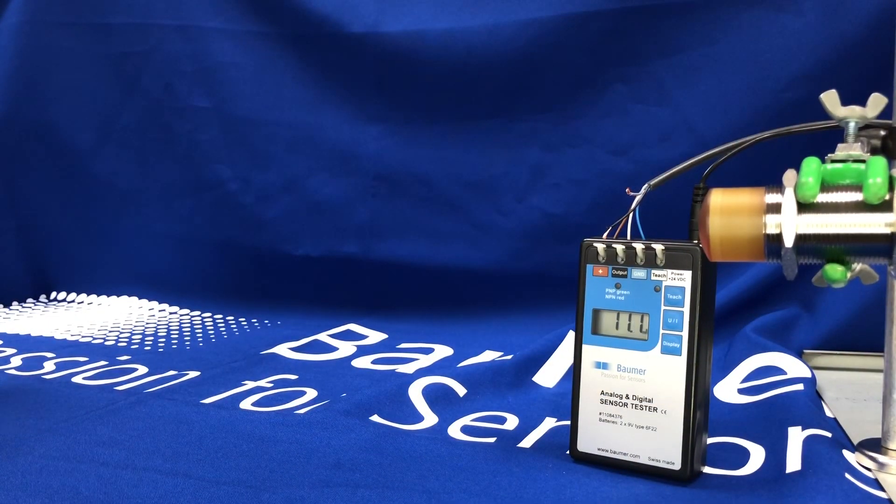To show the analog output, I've set the analog maximum at 800mm, I'm still inside of that, and the analog minimum at 300mm. This is a 4-20mA signal.